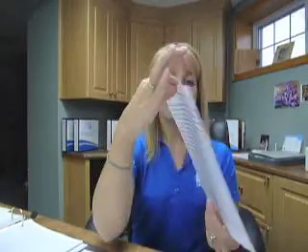Hydrocollator, making sure that the water isn't too hot and is clean, and that the hot packs aren't burst open. When you look at the monthly form, depending on the wax bath and the hydrocollator, you need to check the instruction manual, because all of them are a little bit different as to what the suggested cleaning schedule is.